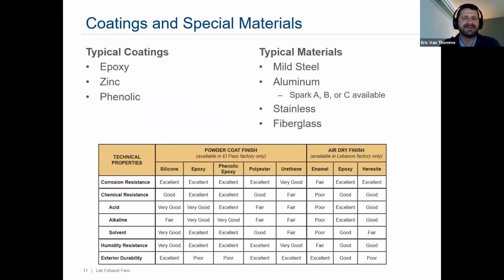Coatings and special materials. All of our fans are produced out of mild steel as a standard, and then we apply one of a variety of coatings depending on the application. We've got a little chart here at the bottom that shows the typical corrosion resistance for the different coatings that we offer. We can also do these lab fans out of aluminum, and we usually incorporate spark type B construction to create a spark resistant construction so that you're not dealing with any of that. So we have that available.